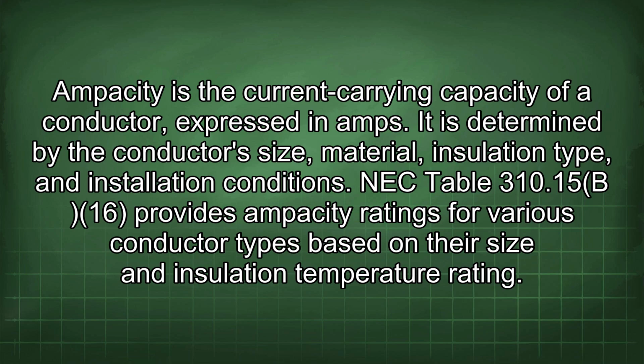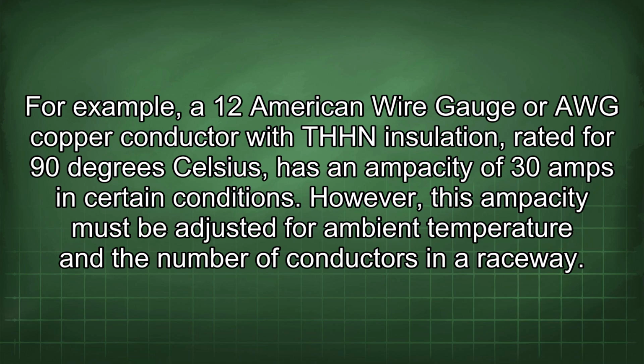NEC Table 310.15(B)(16) provides ampacity ratings for various conductor types based on their size and insulation temperature rating. For example, a 12 American wire gauge, or AWG, copper conductor with THHN insulation rated for 90 degrees Celsius has an ampacity of 30 amps in certain conditions. However, this ampacity must be adjusted for ambient temperature and the number of conductors in a raceway.